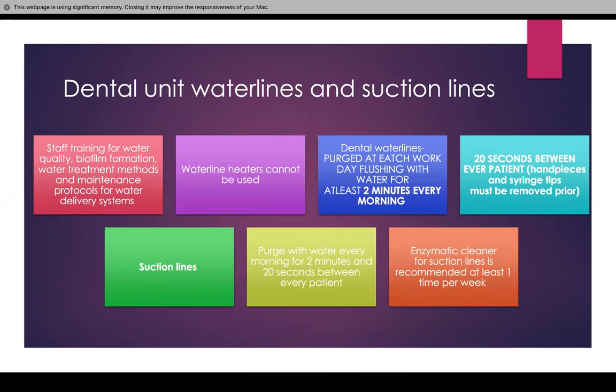Dental water lines must be purged at each workday by flushing with water for at least two minutes every morning. You have both suction lines and handpiece lines, and these must be flushed for two minutes every day. Between every patient, handpieces, syringe tips, and everything must be flushed for 20 seconds. Suction lines also have to be purged every morning for two minutes and 20 seconds between every patient, and you also have to have a log. An enzymatic cleaner for suction lines is recommended at least once per week.